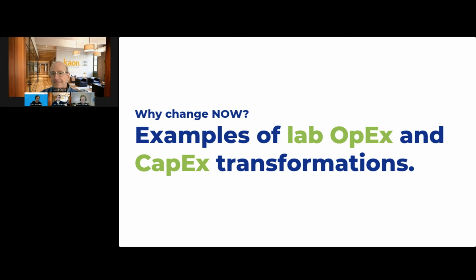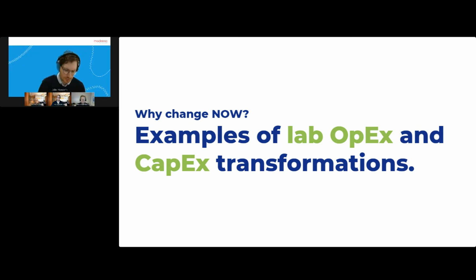Sure, I'm happy to speak about a new system we've been looking at for equipment monitoring. So we've had equipment monitoring for years, but never to the level that we're looking at now. We have several thousand pieces of equipment within our research environment in Cambridge, Massachusetts, and we had 20, 30 monitors over the last few years, but in the last year, we're now looking at expanding to about 200. So this would be on all of our mass specs, NMR, flow cytometers, things like that.